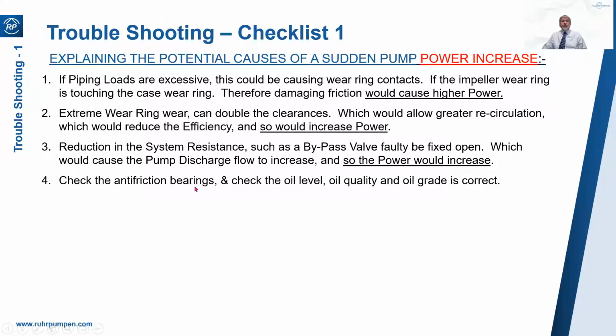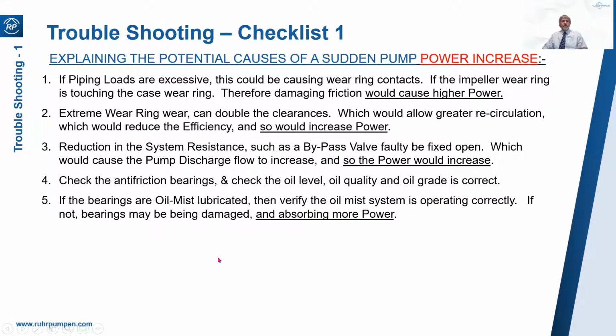Check the anti-friction bearings and check the oil level, oil quality, and that the oil grade is correct. And I would say particularly oil level. Too high an oil level is worse than too low an oil level. I've seen pumps overheat and vibrate badly just because they had too much oil in them. If your bearings are oil mist lubricated, then verify that the oil mist system is working correctly.